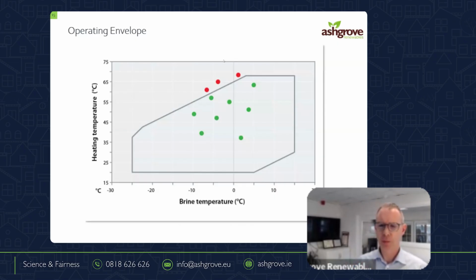So this is an operating envelope. Again, we took it from a Thermia machine, but this will be the same for Stiebel, or it'll be the same for whoever, Viessmann. Might be a different shape, but they will have an operating envelope that looks like this. So when I have two things, in this case, it is a ground source heat pump. You can see here I have a brine temperature.